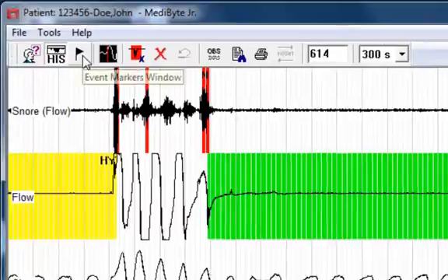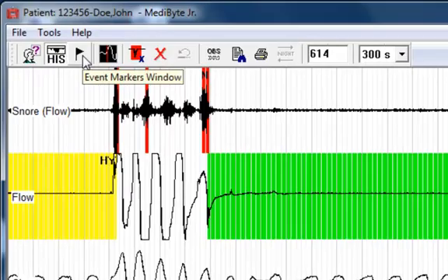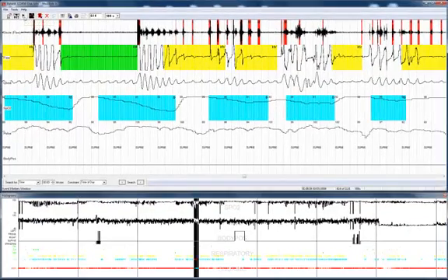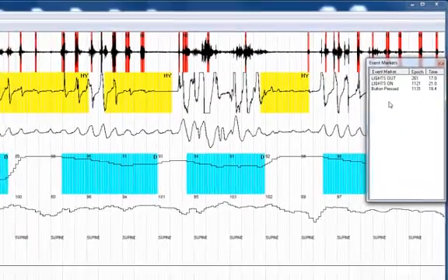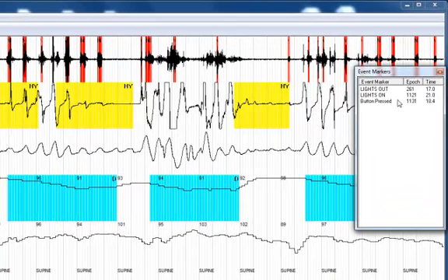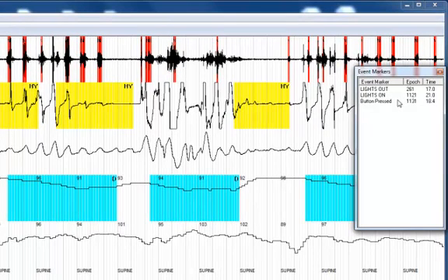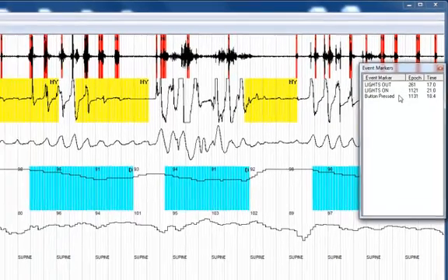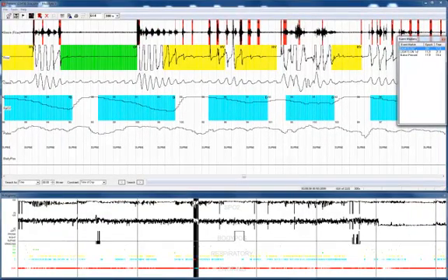The next toolbar icon we will discuss is the event markers window. Click this button and the event markers window will appear. It shows you a list of event markers that are in the recording including lights out, lights on, and if the patient pressed the event button during the recording. To jump to one of these event markers in the recording, select the event marker and double left click on it.